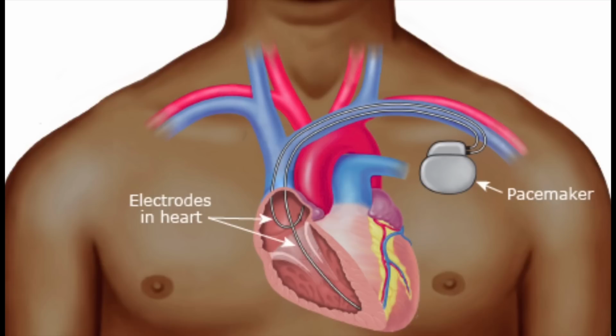The pulse generator for most modern permanent pacemakers weighs 1 to 2 ounces. Flexible insulated wires, or leads, carry electrical impulses from the generator to the heart muscle and relay information concerning the heart's natural activities back to the pacemaker. There may be several such wires, or leads, placed within the heart, most commonly in the right atrium and right ventricle. One type of pacemaker is leadless and does not have any wires. The pacing lead most commonly incorporates 1 or 2 electrical poles.